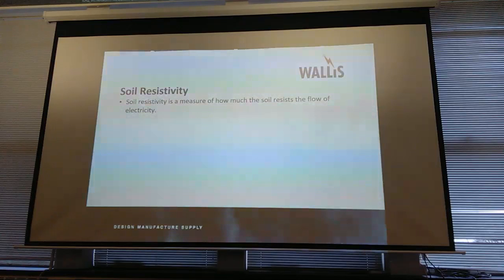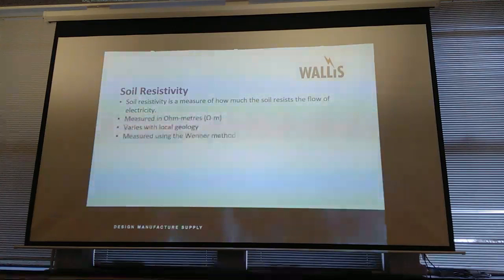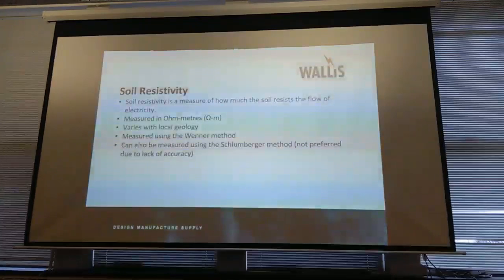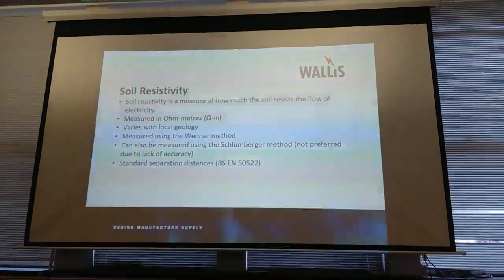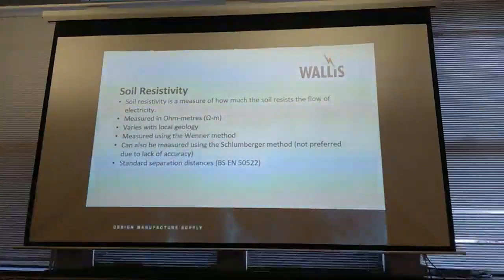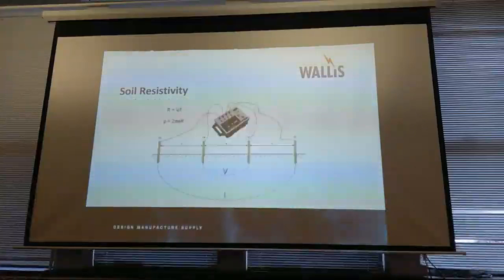So we need to know how many earth rods are going to go into the ground to give us a required value, not less than 1 ohm. Measured in ohm metres, it varies with local geology. We tend to use the Wenner method. There are other methods out there. The Schlumberger method, I think, yeah, I put on there. That tends to be oil and gas. They're all a similar principle, but the standards tend to work around the Wenner method. As described, the standard separation distances are in 50522 as well. That is the standard layout for the Wenner method.